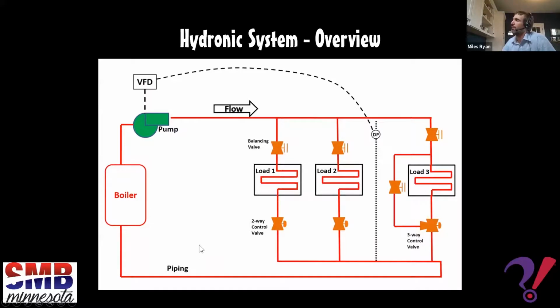All right, so on a primary only system, on this one in particular, it's a variable speed system, meaning this pump can slow down and speed up to meet the flow requirements of the served loads. So let's talk through that. Each load, each heating coil or fin tube radiation, what have you, is going to have an associated control valve. Now, on a system like this, most of those control valves are going to be two-way control valves. These two-way control valves modulate to meet the heating requirements, the requests from this particular heating coil. All right. So if this particular heating coil is satisfied or it's being overheated, its respective thermostat or control is going to tell this valve to start to modulate close.